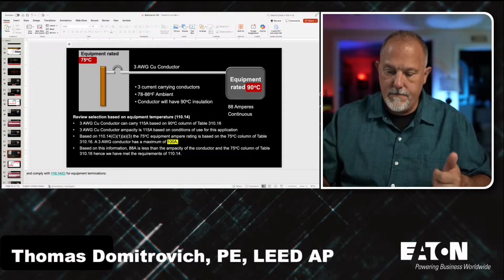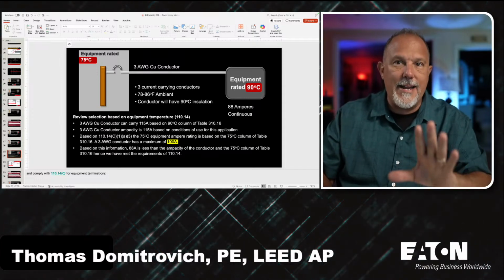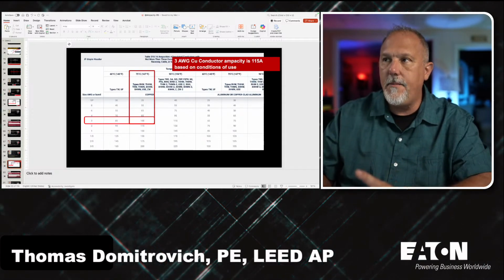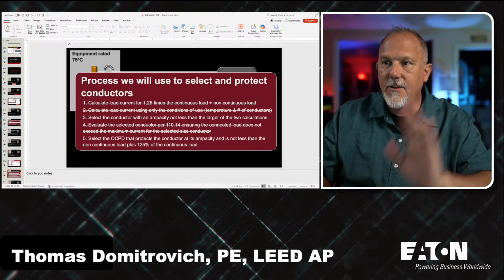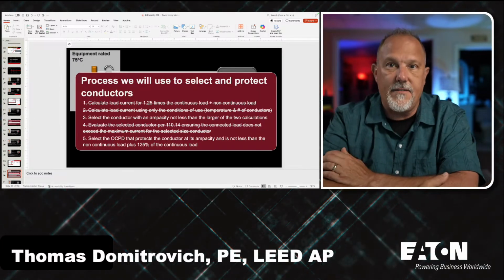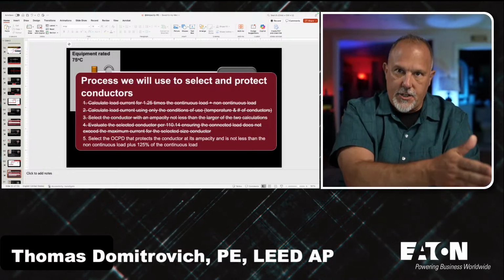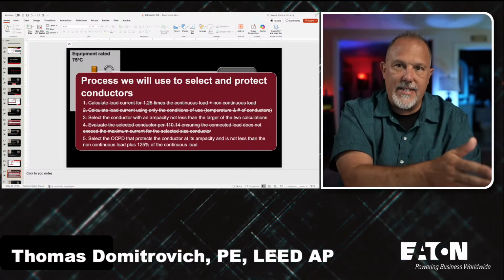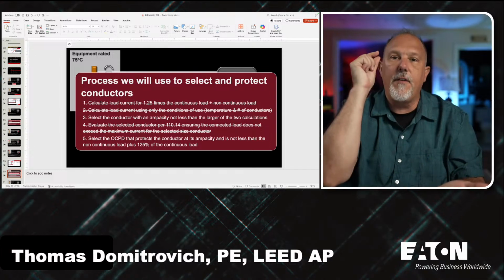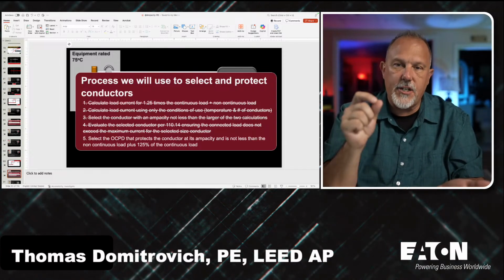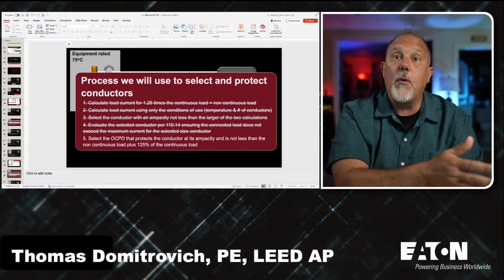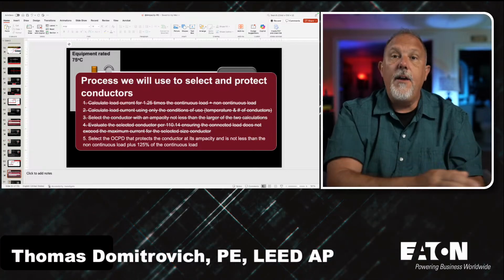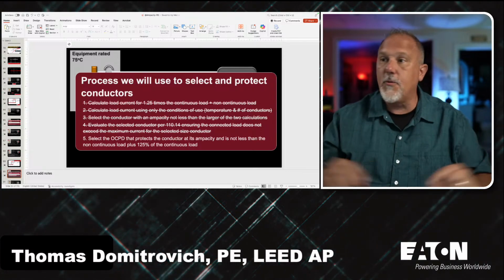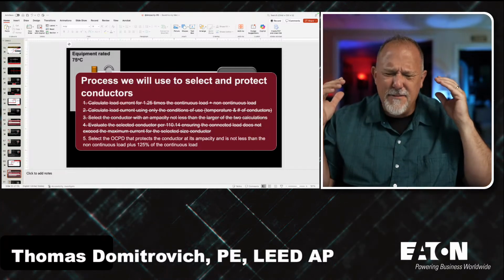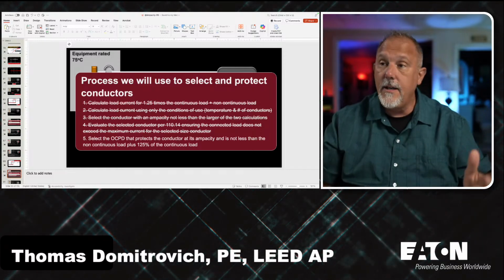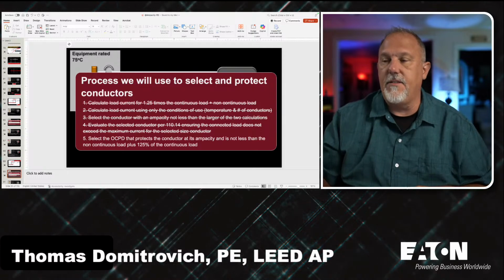Okay, so now follow my logic. I've done all that. Now I have to pick my overcurrent protective device. I know my termination is good. My 88 amps isn't going to exceed the 75-degree C column for that number 3 or 3 gauge conductor. I can handle up to 100 on that 3 gauge. The 3 gauge conductor itself can handle up to 115. You're golden.